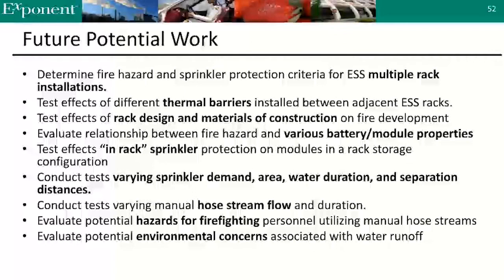As Ben highlighted, we could look further into multiple rack installations, evaluating the effects of different thermal barriers installed between the racks. A very important one is the rack design and materials of construction. For example, is there a roof on the rack? Is there a front door on the rack? We could do further work evaluating the relationship between the various properties of the batteries and/or modules and the fire hazard. If there is a desire to extinguish the fire, in-rack sprinkler protection is an area that could be evaluated further. And of course, varying tests of the demands of the sprinkler system, area, water duration, and separation are obvious areas for future work.